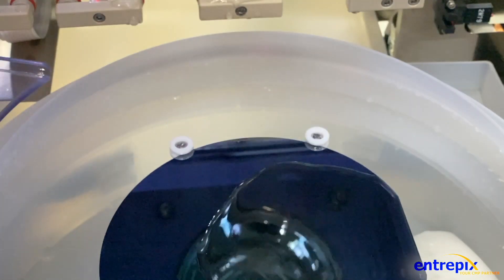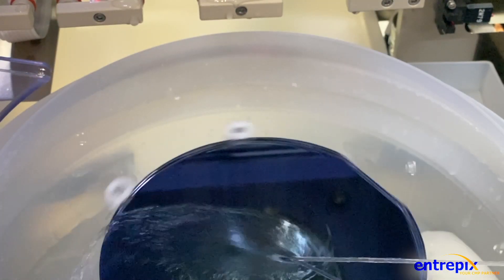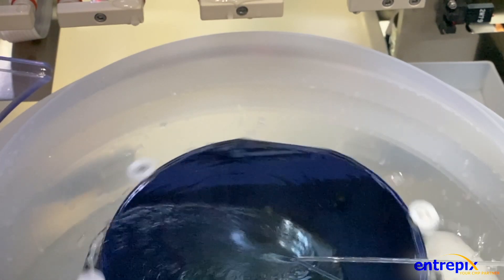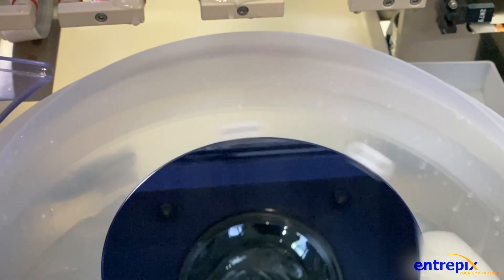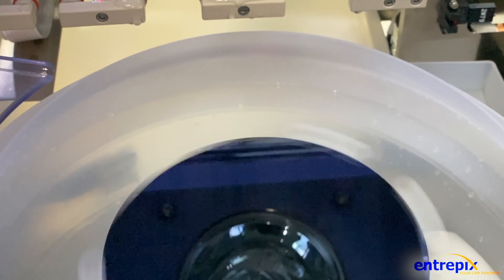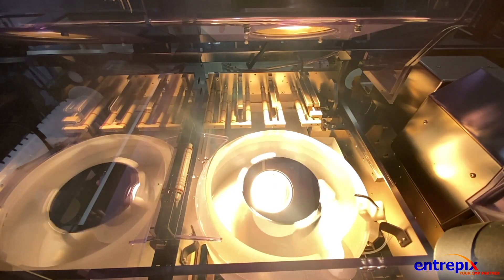After undergoing the cleaning process within the brush box, the wafer moves into the spin station where it runs through a spin-rinse-dry cycle. Improvements from the legacy OnTrak include improved energy focus, lower power consumption, and improved safety features, resulting in a reduction in dry time and enabling increased throughput.